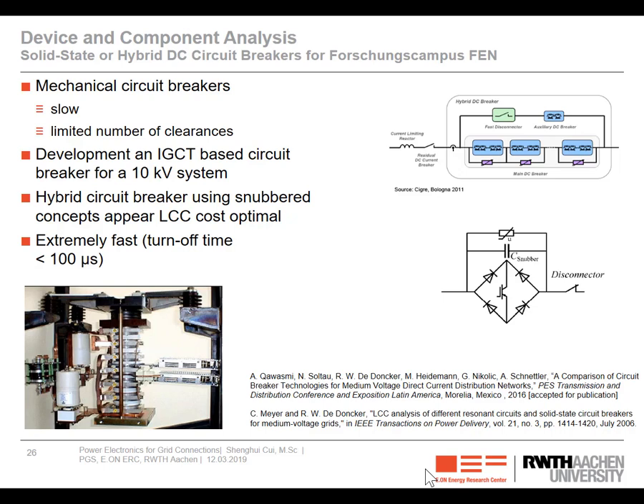So today, for DC circuit breakers, there are two different types. One is the so-called hybrid circuit breaker. Why is it called hybrid? Because in this circuit breaker, there is one electronic current path and also a mechanical current path. That's why we call it hybrid circuit breaker. And here another option is the so-called solid state circuit breaker, as you can see here. But here there's no mechanical current path in parallel.